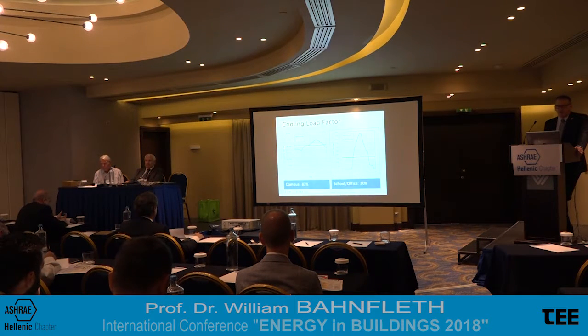Something that's more typical of a school or office, where there's high occupancy for a few hours during the middle of the day and no occupancy at night, is shown on the right, and that's a fairly typical load factor as well, something below 50%, maybe as low as 30%. So there's opportunity in both of them to increase the load factor. Clearly we can do more with the school or office type of load, but actually the large district cooling type of loads turn out to be very good candidates for thermal storage for other reasons, mainly associated with the economics of large systems.